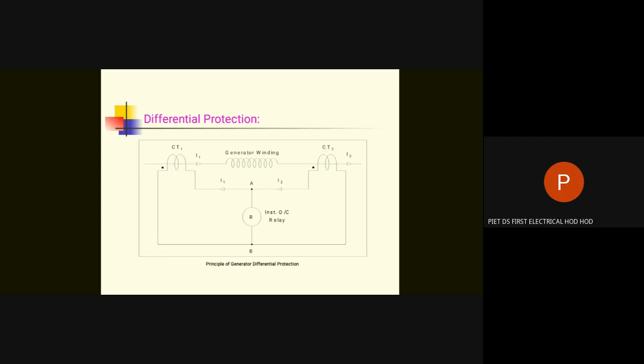So for any kind of protection, we will have to study so many things: the causes of the problem, the consequences of the problem if we don't take action, and the third thing, what is the protective scheme to get rid of these problems? So failure of stator insulation is due to many causes. One very obvious cause is overload. That means if the load of the generator is more than the rated load, a large current will flow, more than the rated current.